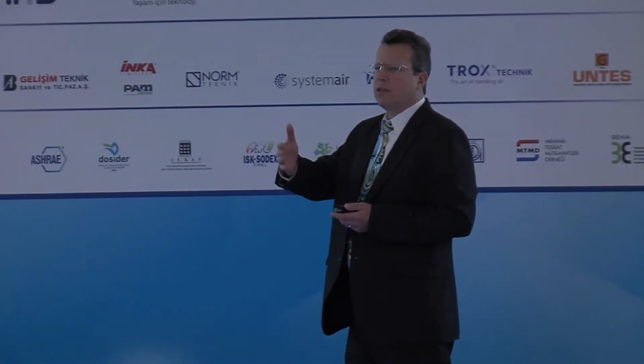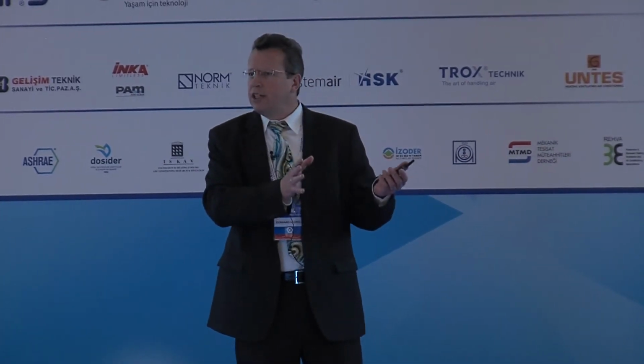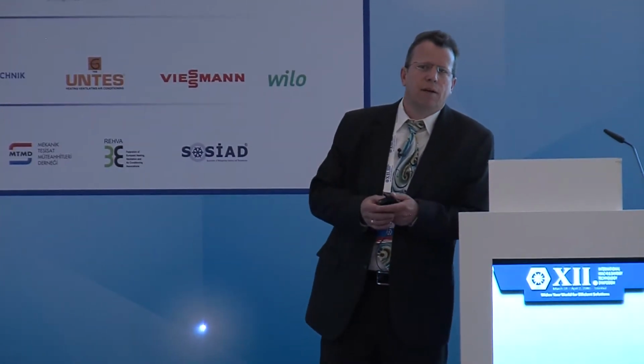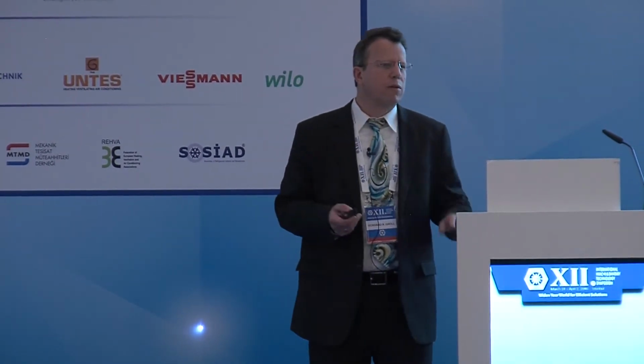The typical trade-off, for example, is when I reduce my clearance, right? I reduce leakage, that's positive, but I increase friction, that's a negative. And you'll find that for every compressor design there is a sweet spot where you get the optimum performance. And that's what we're after when we design these compressors, and this type of model will allow you to do exactly that.